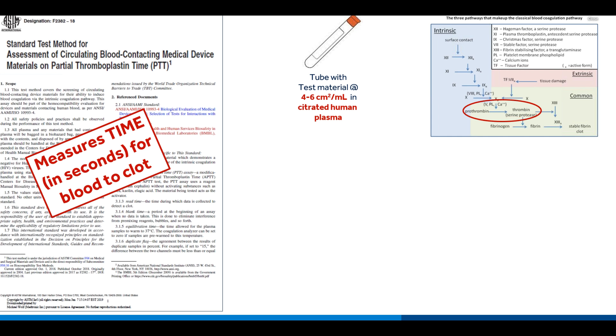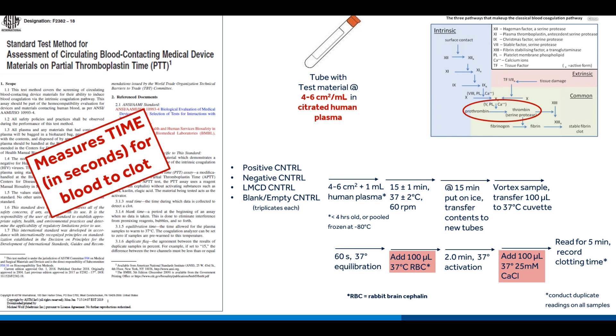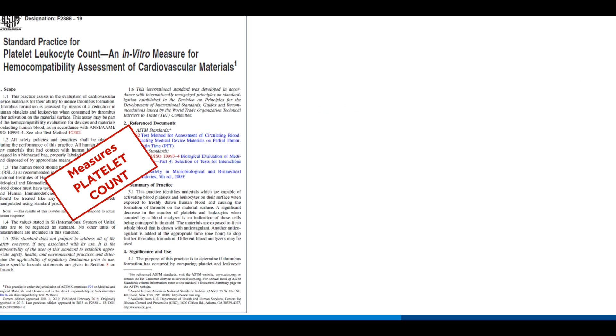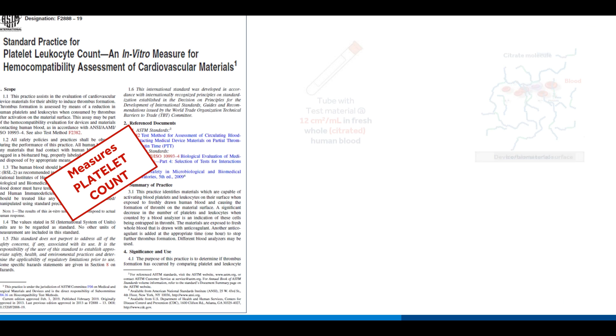And after a certain amount of exposure and the addition of this thing called rabbit brain cephalin, and then the addition of calcium are two big steps that make the assay work, but it's a very simple test, and in the end you end up with the amount of time it took for a clot to form. And the other test is also very simple. It only measures platelet counts. It's sort of a misnomer. It's called a platelet leukocyte count test, but in the standard, it admits somewhere towards the end that the leukocyte data workup is not always necessary, because there hasn't been any validation done to the interpretation of that part of the test. So people really only use it to look at platelet count.